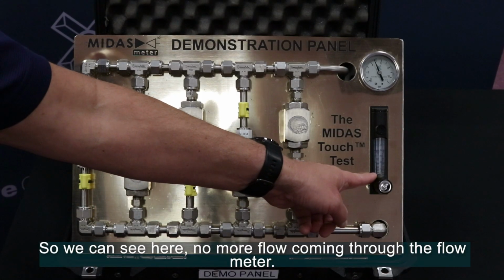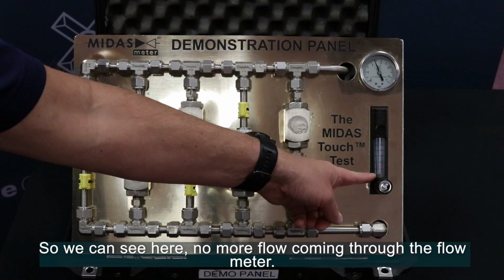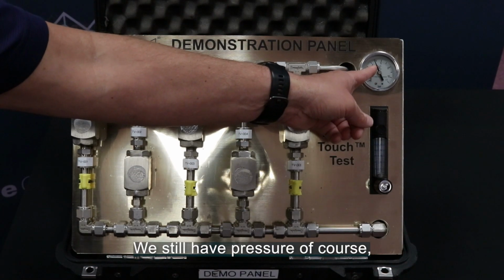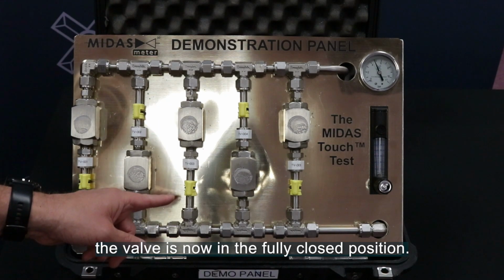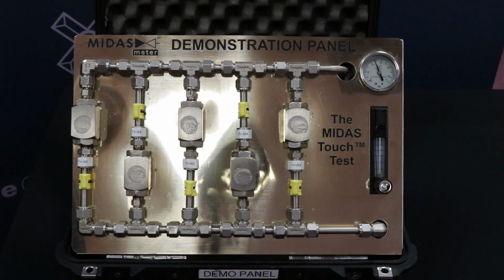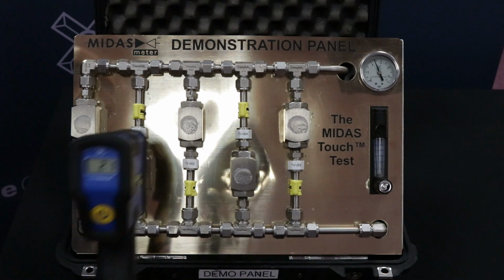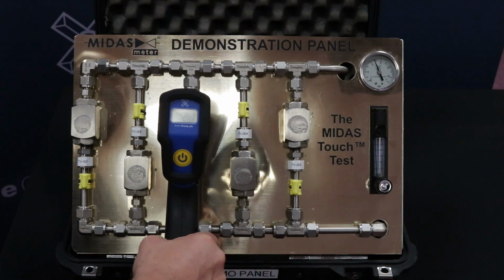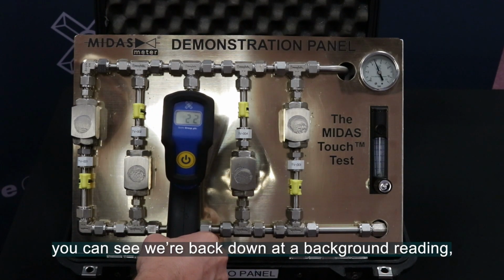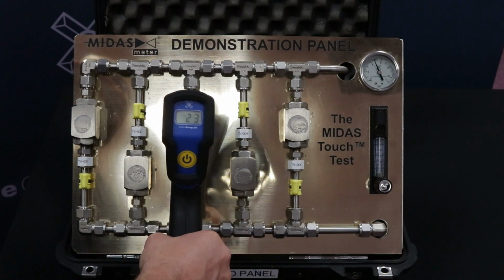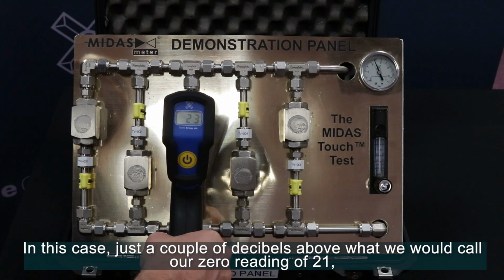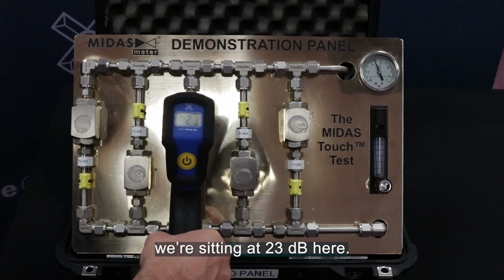So we can see here, no more flow coming through the flow meter. We still have pressure, of course. Valve is now in the fully closed position. If we come on with our MIDAS meter, you can see we're back down at a background reading. In this case, just a couple of decibels above what we'd call our 0 reading of 21. We're sitting at 23 decibels here.